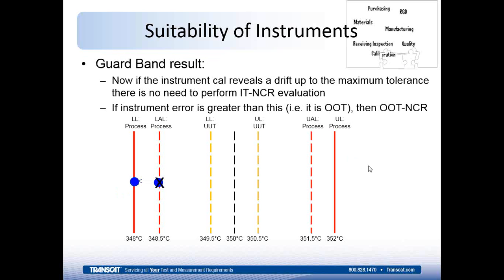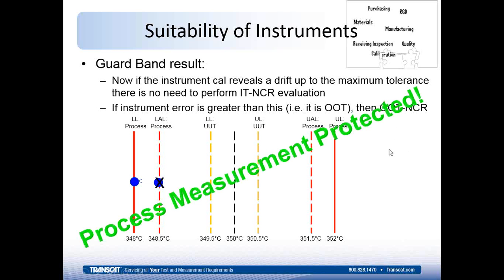So the result is, even if that instrument drifts, its error is not greater than the measurement process would allow for these upper and lower acceptance limits that are inside the upper and lower process limits. And that protects the measurement.